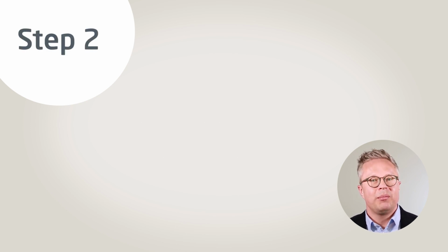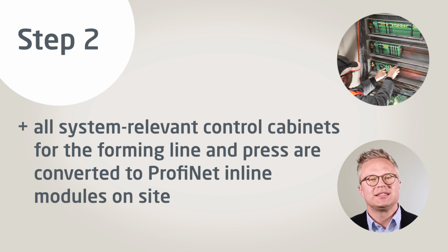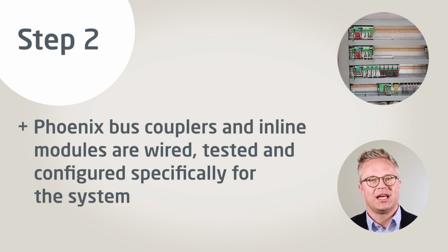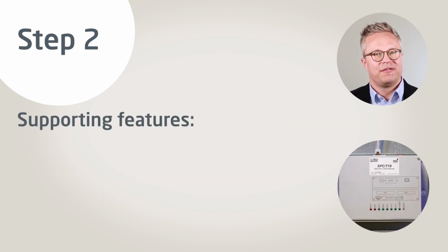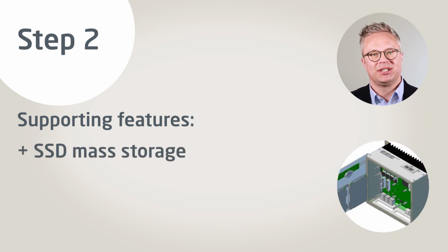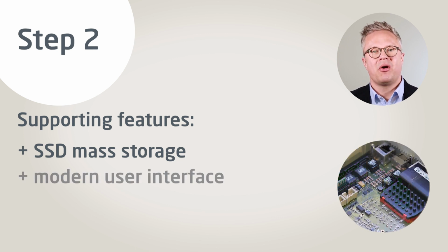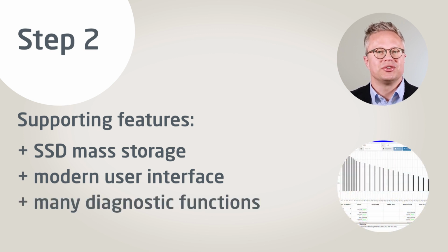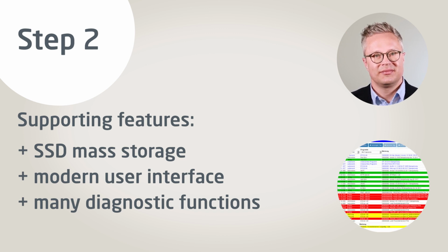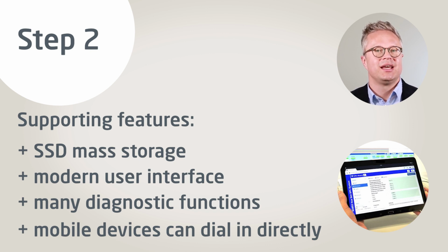Step 2. If the complete Interbus communication is replaced, all system-relevant control cabinets for the forming line and press are converted to Profinet inline modules on site. In the process, the Phoenix bus couplers and inline modules are wired according to the circuit diagram, tested and configured specially for a system. This speeds up recommissioning and avoids unnecessary downtime. This is supported by the following features. The SSD mass storage used for log data storage. A modern user interface for all browser types. Many diagnostic functions for pressure, position control and other maintenance functions. And a smart solution, mobile devices can dial in directly to the system.